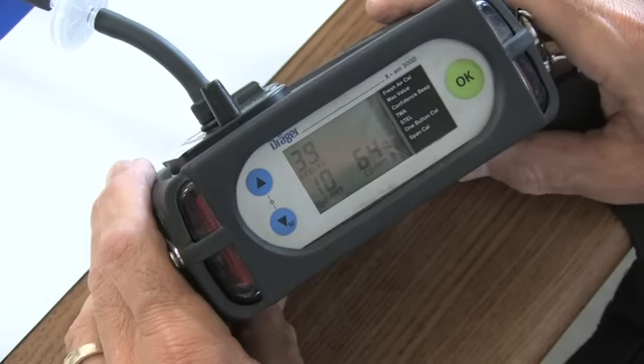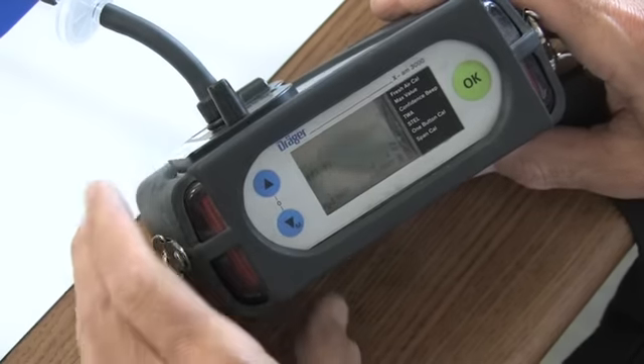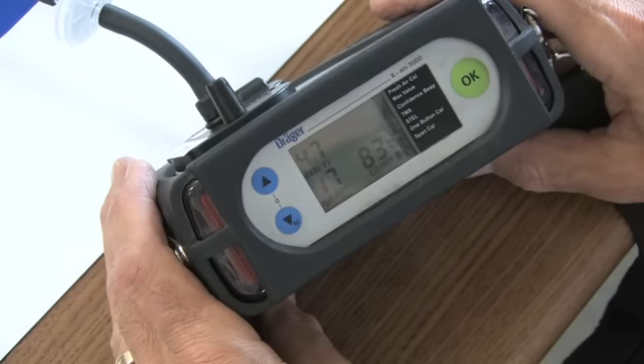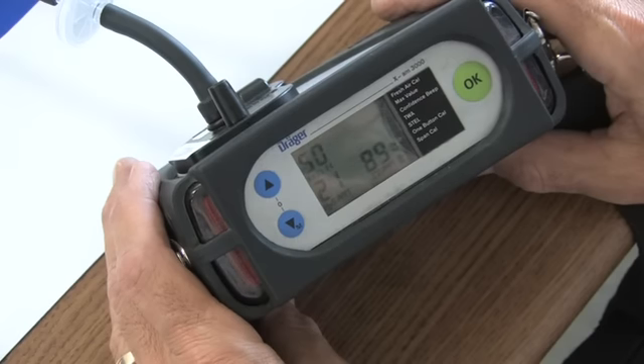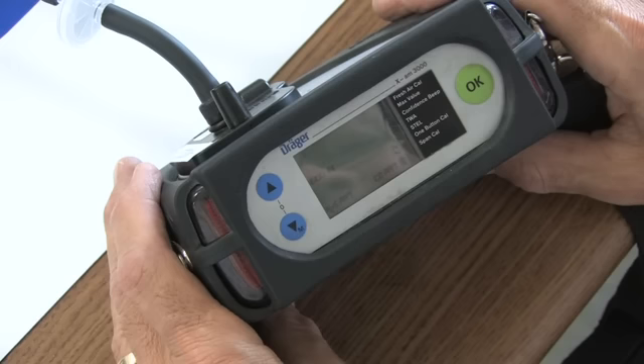So there we go, we're getting our movements again. Wheatstone bridge sensor is really healthy in this meter. Waiting for it to go up. H2S almost hitting the 20 marker. These sensors did well on the bump test, but I want to go ahead and just zero in the calibration. 91, 22, 52. So the numbers look like they've stabilized pretty good.